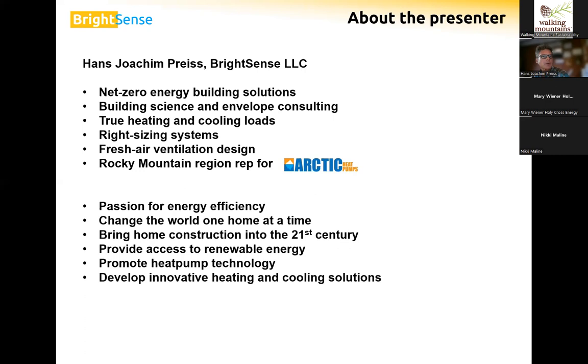Right sizing: boilers or furnaces have been greatly oversized. Traditionally, just to be on the safe side, it was better to have this 8-cylinder in your basement instead of a small turbocharged 4-cylinder. That at least years ago was what people were doing. But that led to short cycling, temperature swings, and high energy consumption. So now we are right sizing. As you will see further down in the presentation, sometimes we might actually be undersizing, putting in a piece of equipment that's too small for the load, but that's perfectly fine, as you will see.